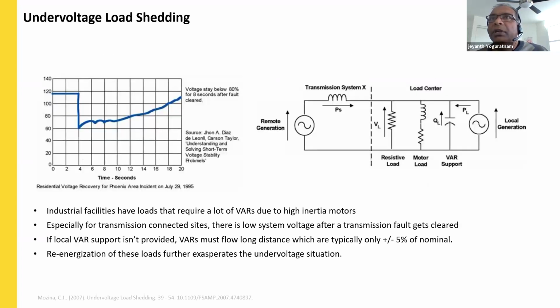So this is another under voltage load shedding example, one of the examples seen in certain cases. Industrial facilities consume a large amount of reactive power in order to power up high inertia motors. In certain cases, if some loads are directly connected to the transmission line and there is a transmission fault, then after clearing the fault the transmission line takes some time to stabilize its voltage, the system voltage. During that time, if we try to energize certain loads, which can bring the voltage further down, the only remedy is to shed some of the load in order to bring the voltage back to normal.